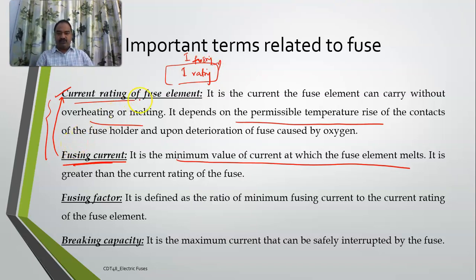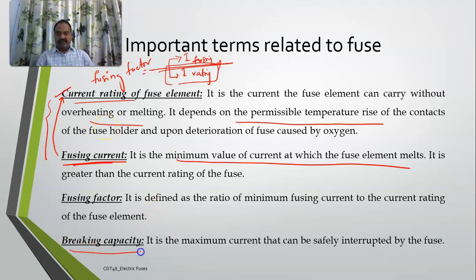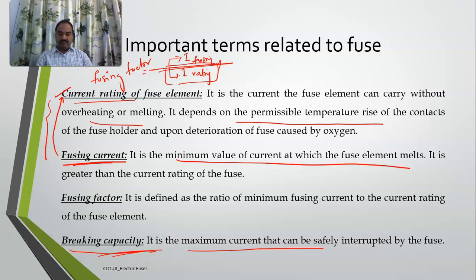The ratio of fusing current to the current rating of the element is called the fusing factor. There is also one more term called breaking capacity, which is the maximum current that can be safely interrupted by the fuse without burning out. To summarize: current rating is the current a fuse element can carry without melting; fusing current is the minimum value at which melting starts; their ratio is the fusing factor.